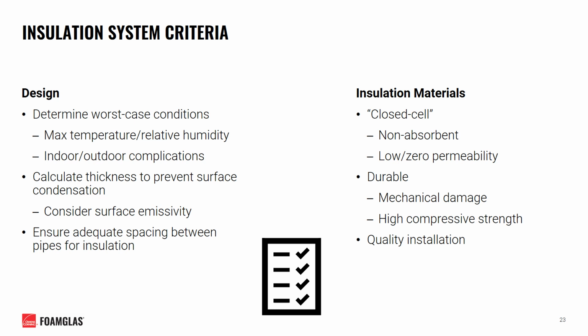When selecting an insulation material for a high-risk environment, consider a material that is closed cell and non-absorbent, with a low to zero water vapor permeability rating. It should be durable enough to tolerate its environment and have a compressive strength to withstand any weight that will come to rest against it, especially for direct burial and pipe support applications. And finally, proper installation and inspection should be carried out during construction to ensure the system is properly installed and sealed against moisture intrusion.